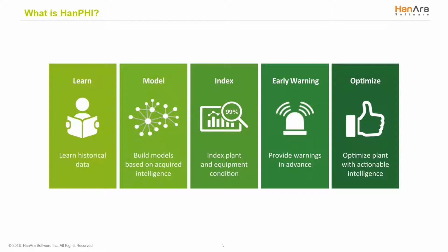As previously mentioned, the predictive data model uses fault-free, normal operation data collected and stored by the historian. Here, the variables are read, and the model executor then calculates expected values, residuals, and health index of each process variable, piece of equipment, and the entire plant. But information isn't useful unless it's easily accessible and understandable. So the solution displays the health index in intuitive hierarchical order to help focus the user on the root cause variable. And if the solution detects an anomaly, an early warning is generated.